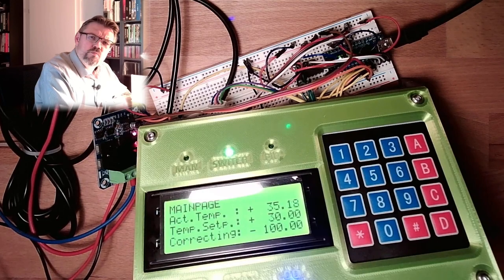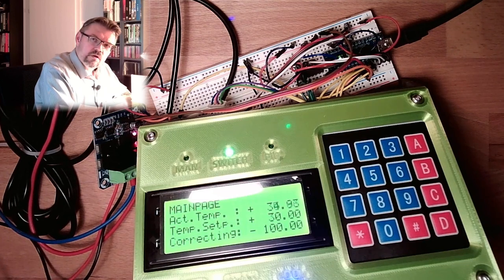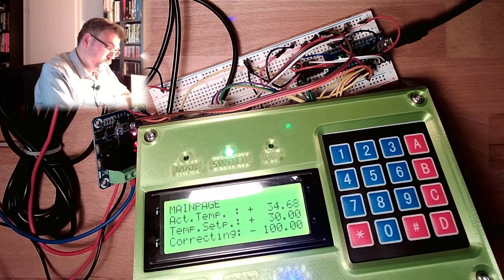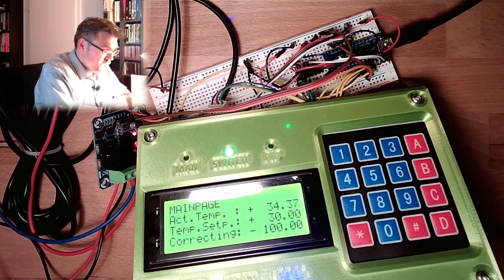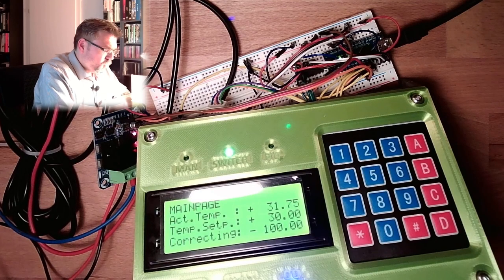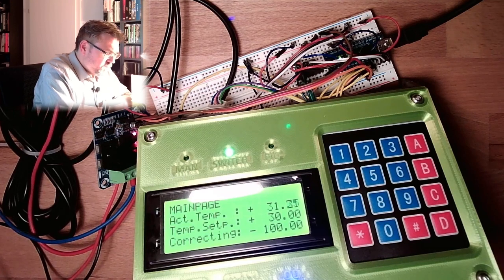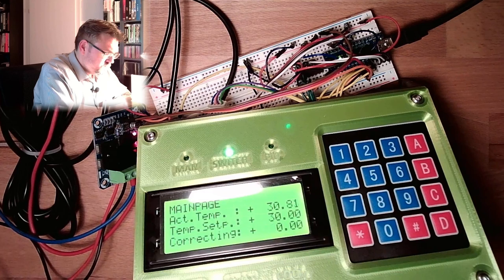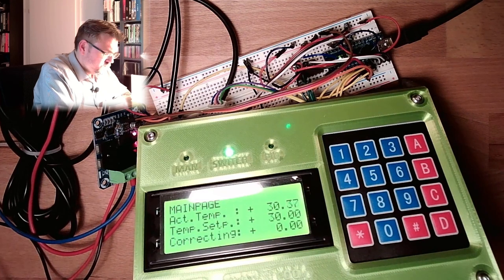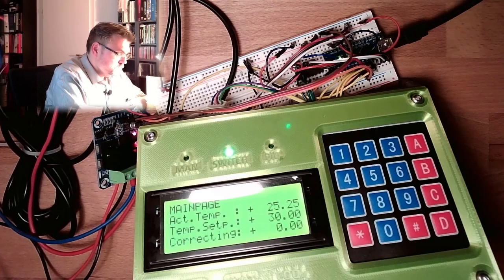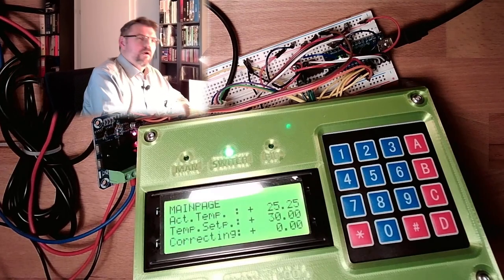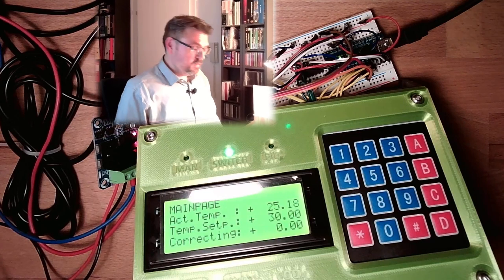And at 31 degrees we should see the cool turned off. Actually it's not a 2 point controller, it's a 3 point controller, because we have cool, heat, and do nothing. And now if we are dropping below 31 degrees, we should see that the cooling is turned off.